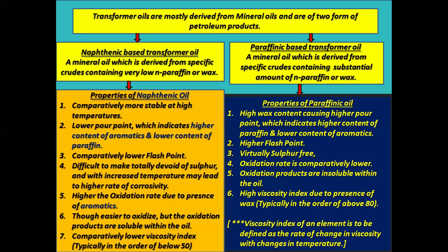Higher oxidation rate due to presence of aromatics, that is aromatic hydrocarbons, though easier to oxidize, but the oxidation products are soluble within the oil. Comparatively lower viscosity index, typically in the order of below 50.